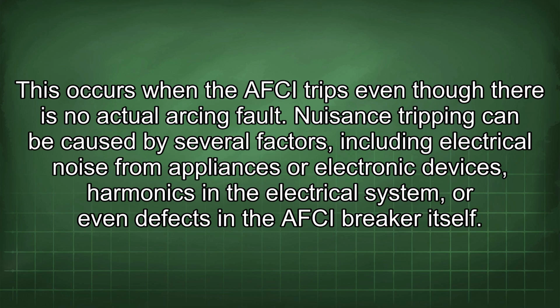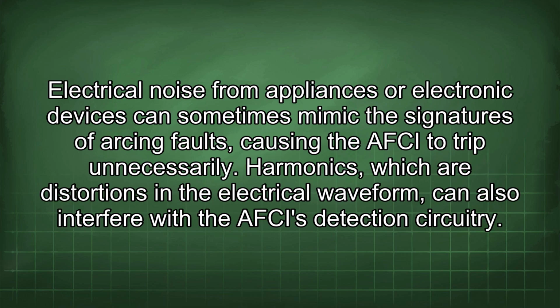Nuisance tripping can be caused by several factors, including electrical noise from appliances or electronic devices, harmonics in the electrical system, or even defects in the AFCI breaker itself. Electrical noise from appliances or electronic devices can sometimes mimic the signatures of arcing faults, causing the AFCI to trip unnecessarily. Harmonics, which are distortions in the electrical waveform, can also interfere with the AFCI's detection circuitry.